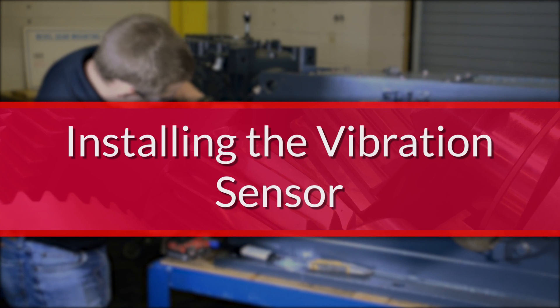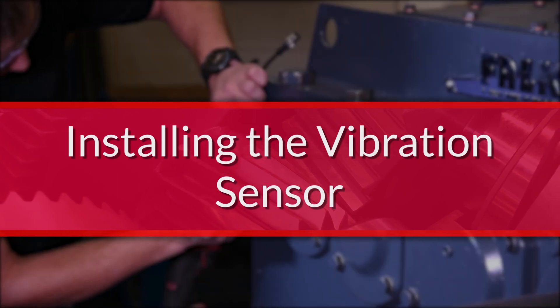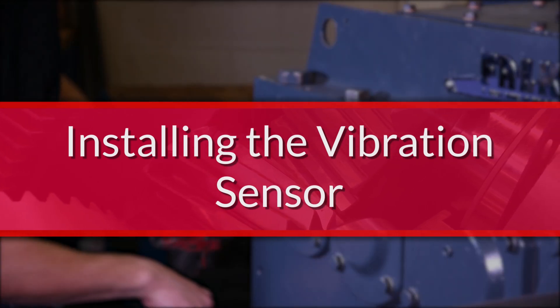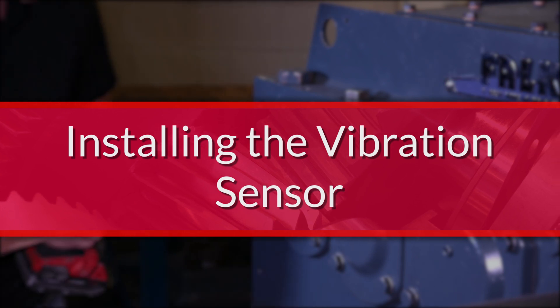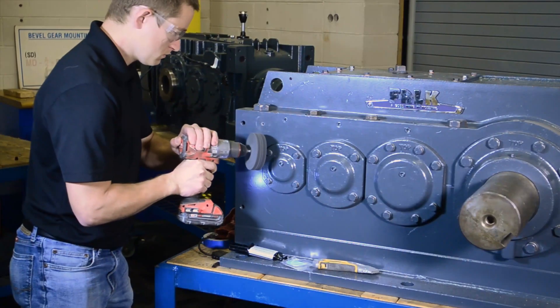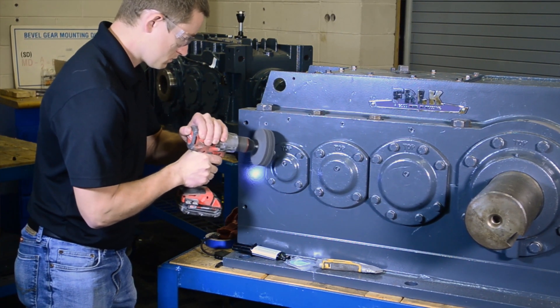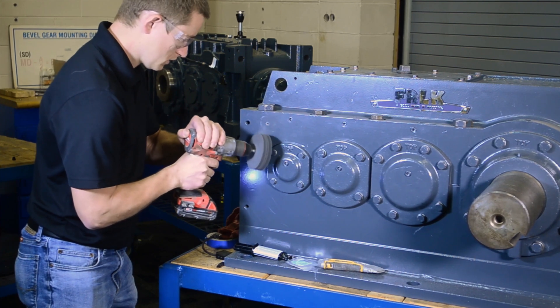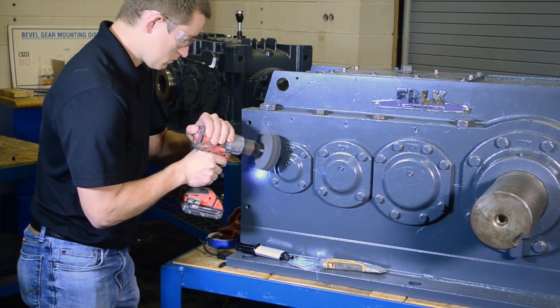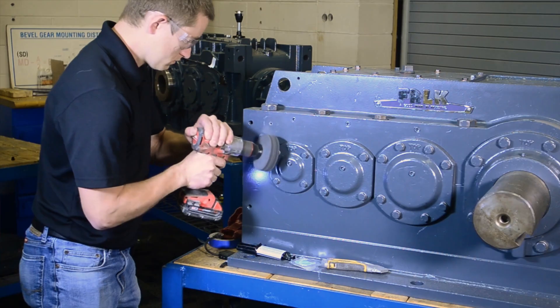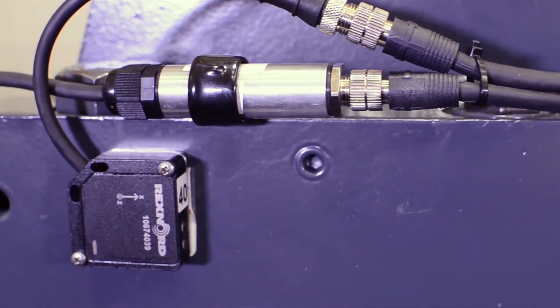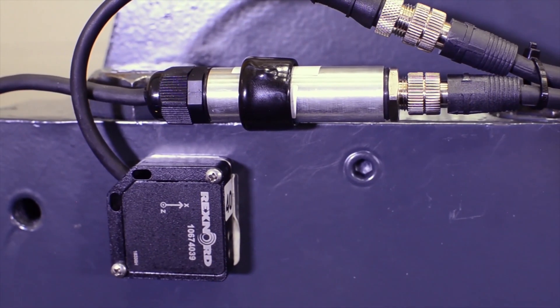The vibration sensor will be installed near the high-speed end of the drive. The preferred side is where the motor couples to the gearbox. For V-Class drives, refer to the installation documentation included in the Model 1010 or 1030 Universal Kit that specifies the correct position of the vibration sensor. Proper orientation is critical to the function of the sensor.